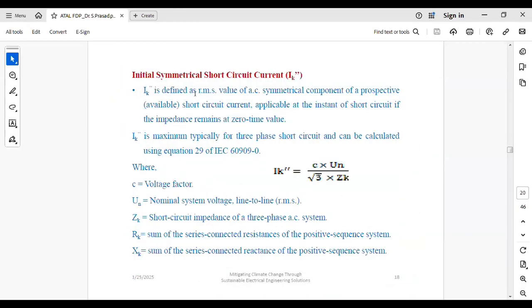So this is Ik double dash, which is nothing but the RMS value of the AC symmetrical component of a prospective short circuiting current, applicable at the instant of short circuit if the impedance remains at zero time value. This value we are calculating according to IEC 60909. This is the standard we follow when conducting the short circuit analysis.